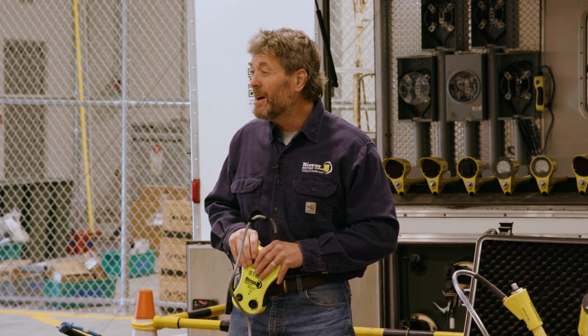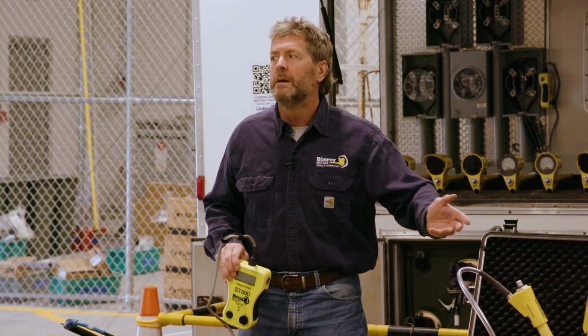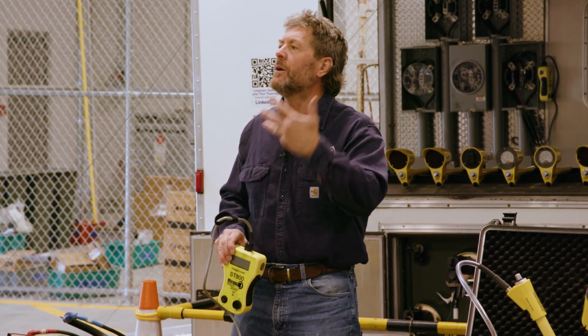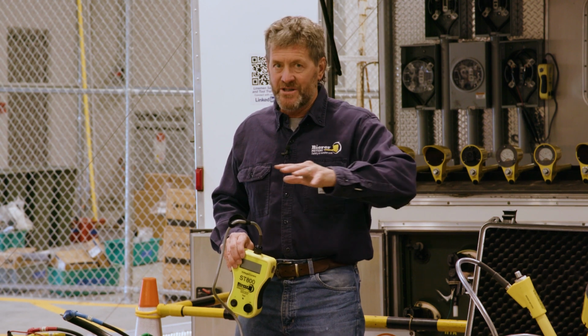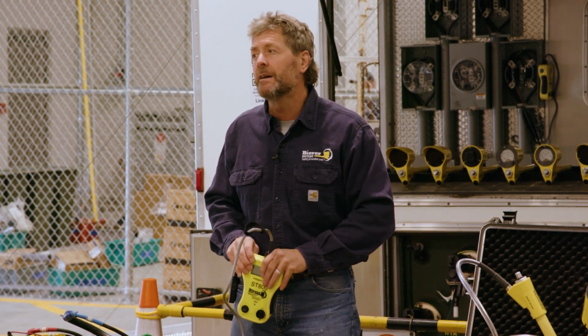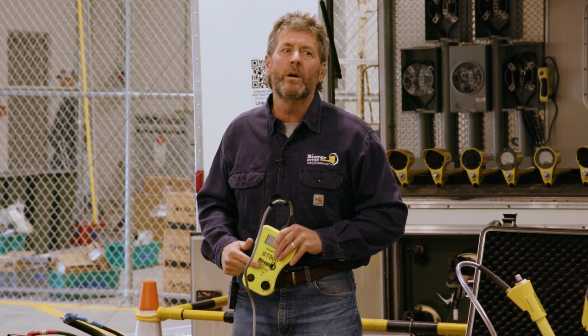You're going to be proactive. You might have a problem that takes 300 amps to find. So you make that repair, then go back and retest it. This time it goes to 800 and holds, so that circuit is now good. That's not uncommon, because now you're sourcing more load.